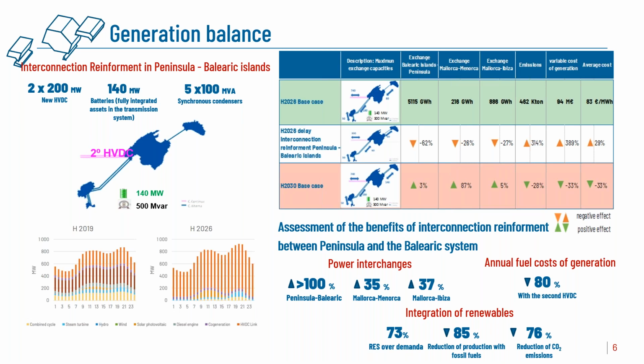Nowadays, the Balearic Islands are connected to the peninsula through an existing HVDC link. The proposed reinforcement consists of installing a second HVDC link of 400 megawatts capacity, along with a set of batteries of 140 megawatts and synchronous condensers. This new HVDC link will increase the interconnection capacity between the islands and the Iberian Peninsula, and therefore the continental European synchronous system.